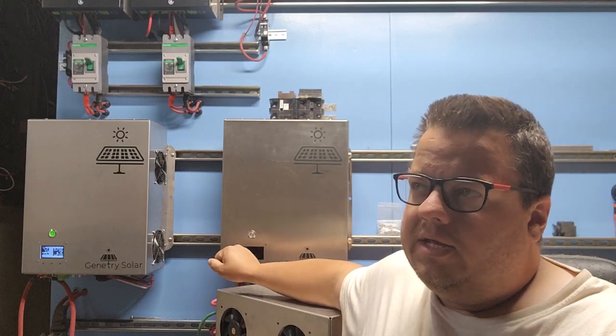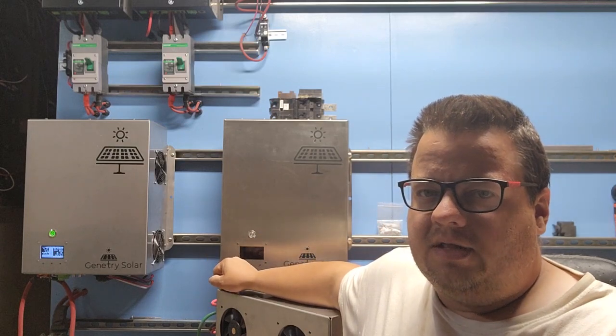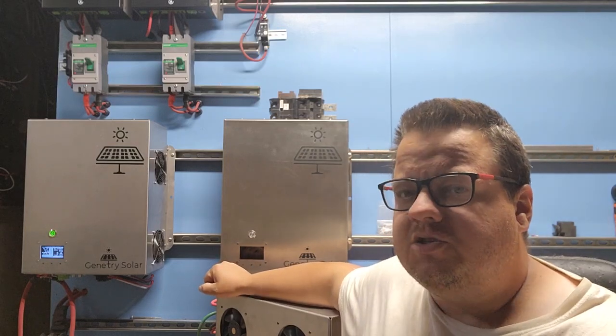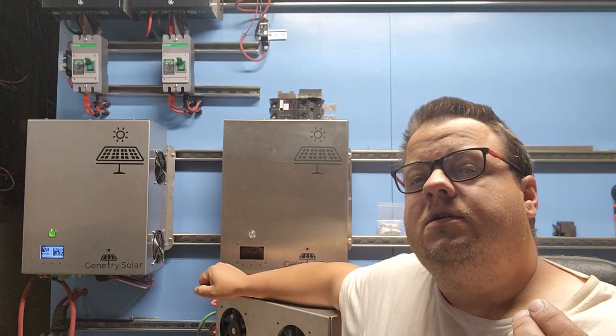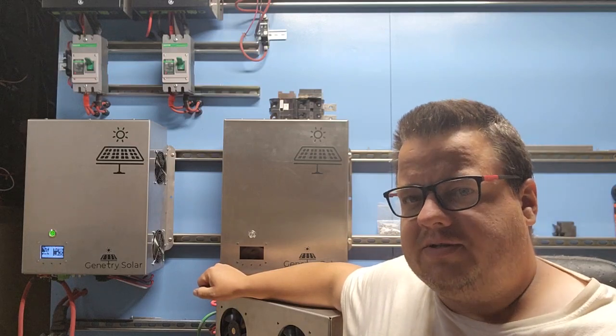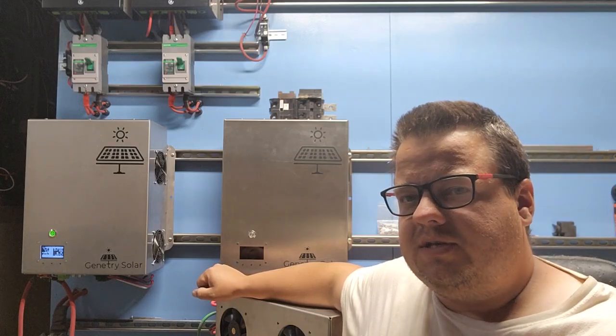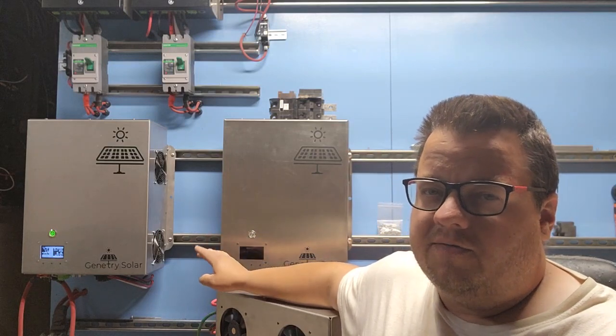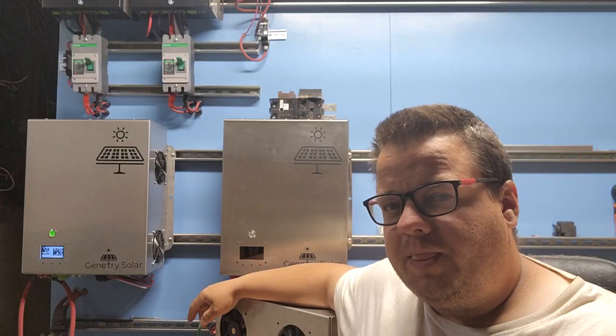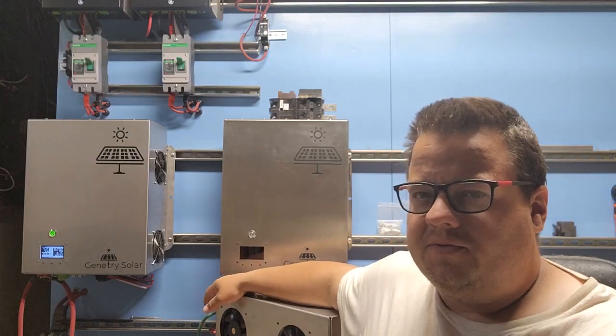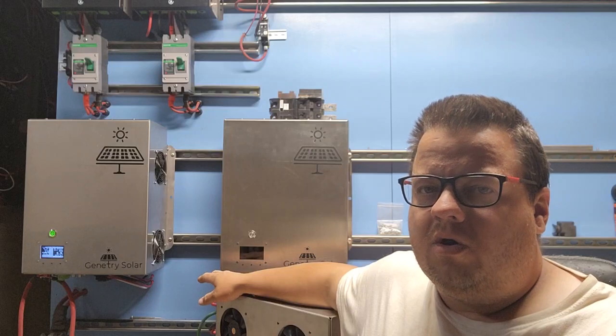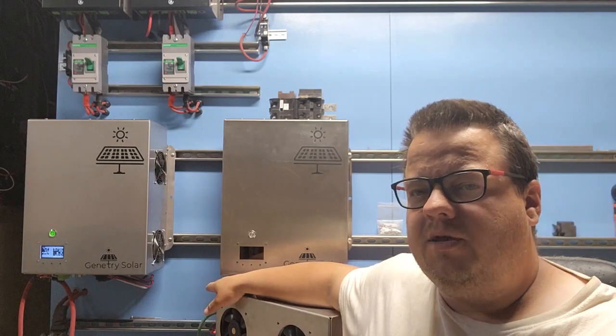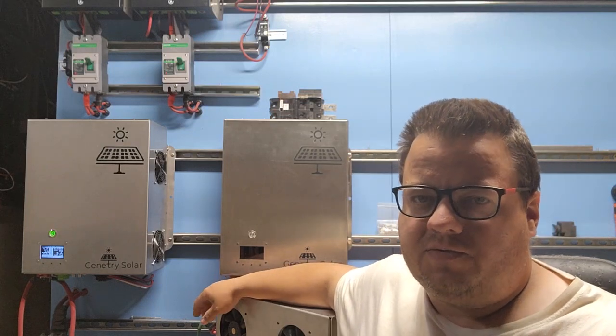The only negative side of the 6 kilowatt inverter is it has a higher resistance transformer. Smaller windings, smaller connectors, there's more resistance there. So the efficiency isn't as good as a 12,000 watt unit. The 12,000 watt unit, we're averaging about 90 to 92%. This is closer to 85%. It's not the end of the world, but just something to be aware of. You're going to be consuming a little bit more energy with the 6 kilowatt just because of the higher resistance transformer.